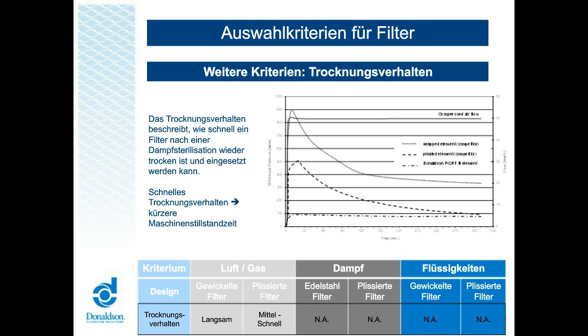Entschuldigung, wir hatten hier einige Probleme mit unserer Telefonleitung. Das Trocknungsverhalten eines Gasfilters beschreibt den Prozess, wie lange es dauert und welche Differenzdrücke auftreten, wenn ein Gasfilter nach einer erfolgten Dampfsterilisation wieder komplett trocken ist und seine Arbeit wieder aufnehmen kann. Auf dem Chart sieht man die Unterschiede zwischen gewickelten Filterelementen und plissierten Filterelementen. Gewickelte Filterelemente werden im Allgemeinen sehr langsam trocken, während plissierte Filterelemente ein sehr viel schnelleres Trocknungsverhalten und somit eine kürzere Maschinenstillstandszeit zeigen.